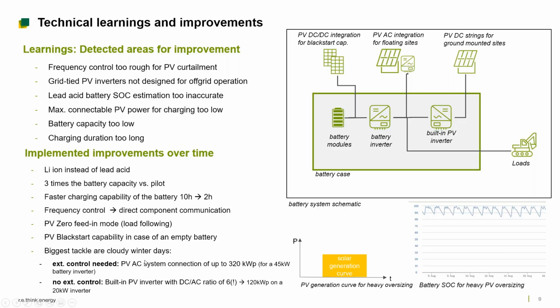But the biggest tackle were actually the cloudy winter days. Since, as I explained, we want to run 100% on solar in any condition, these cloudy winter days are quite challenging, and therefore we designed 2 solutions. First one is including that PV-AC system for the floating sites with external control. We have the possibility now to connect up to 320 kilowatt peak on only a 45 kilowatt battery inverter for charging. So quite a heavy oversizing of PV versus battery charging capability, but solar power is there. We just need to make it usable.